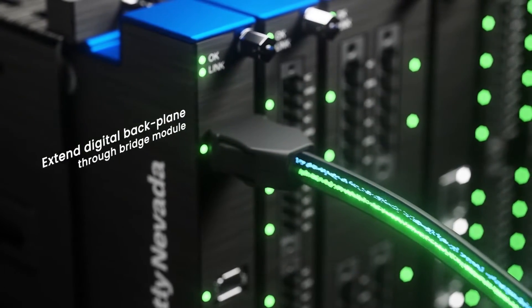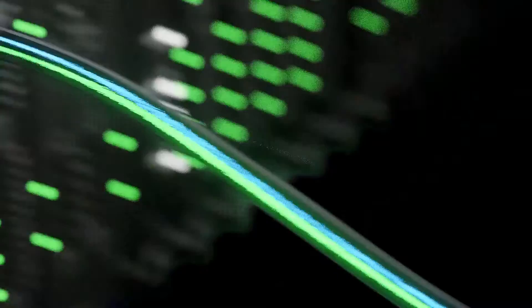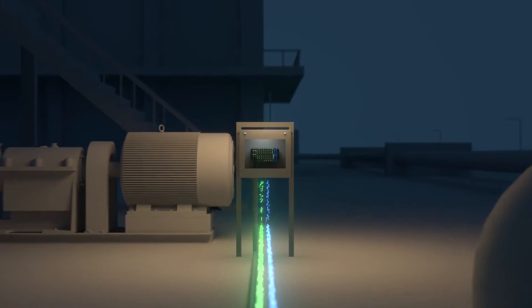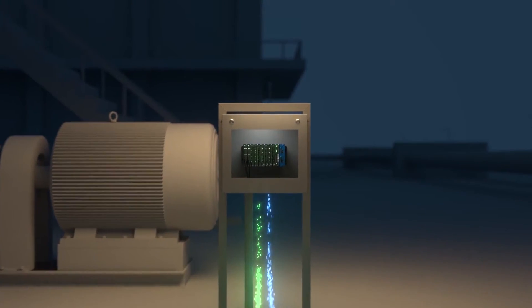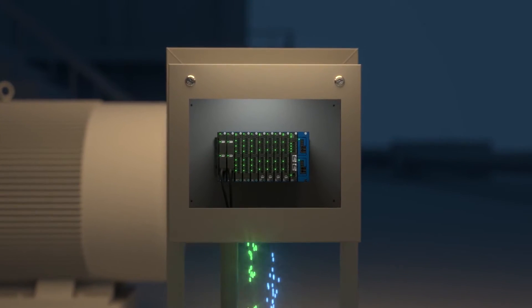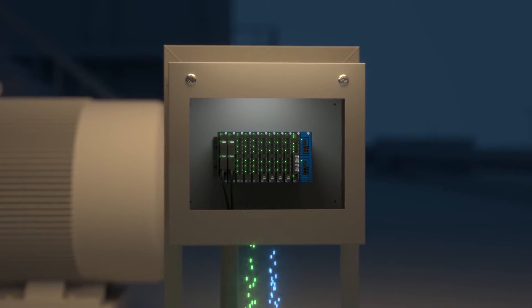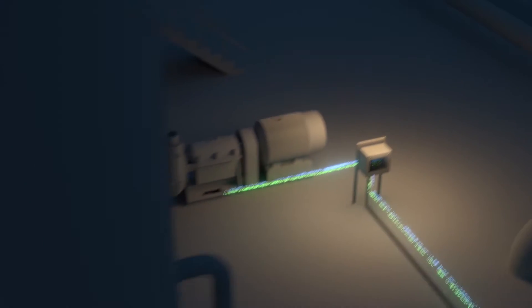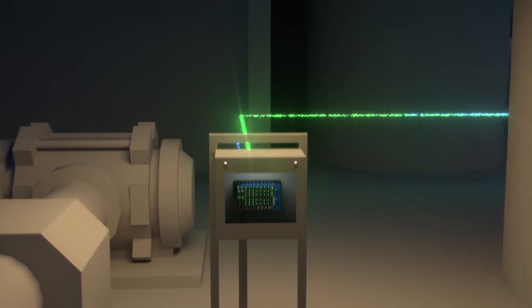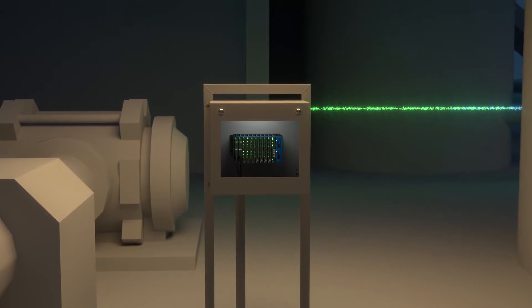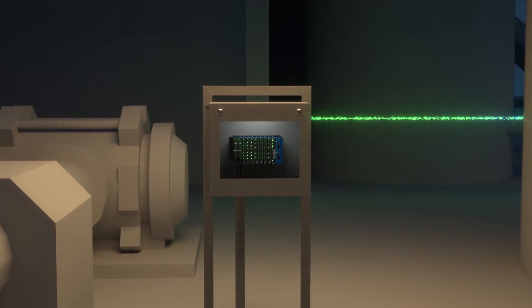I think most people when they think of Bentley Nevada refer back to the 3500. In that system, every four channels of monitoring would have a monitoring card that went in the front and an input card in the back. Essentially you had a processor for every four channels.